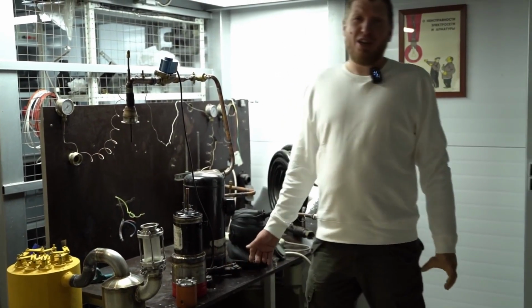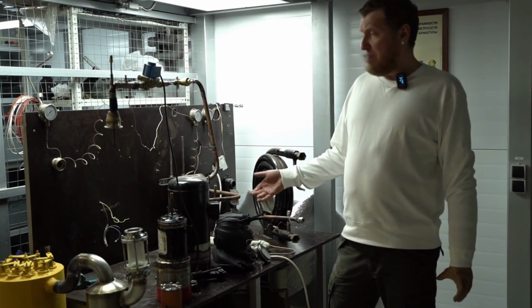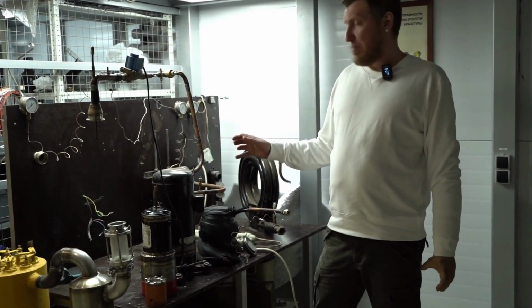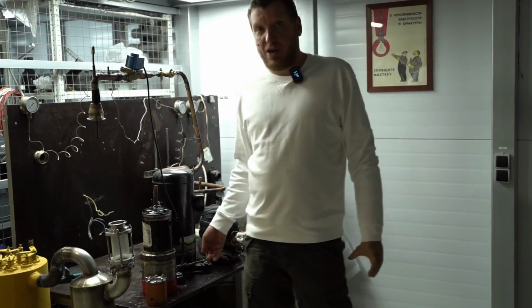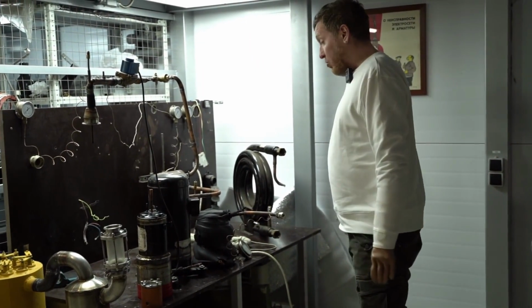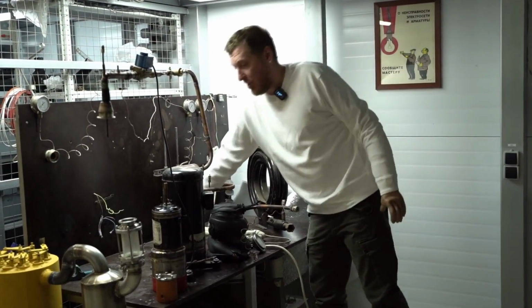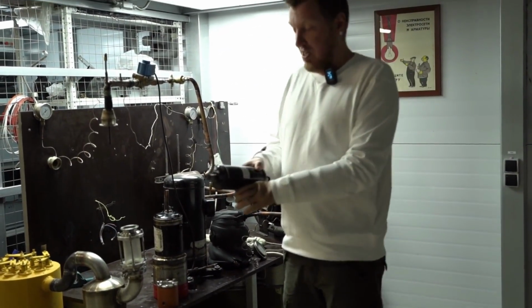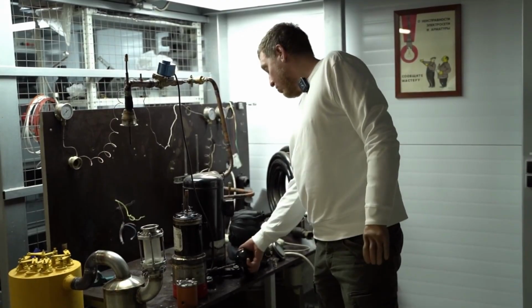The good thing about a gear pump is that even if the vapor phase gets through, it quickly spits it out because of the airiness. It can generate a decent amount of pressure. In other words, it can easily push out 20 bar, no problem. There will also be filters installed here. We'll use refrigeration filters since they're suitable for the pressure. Also pressure gauges and so on.